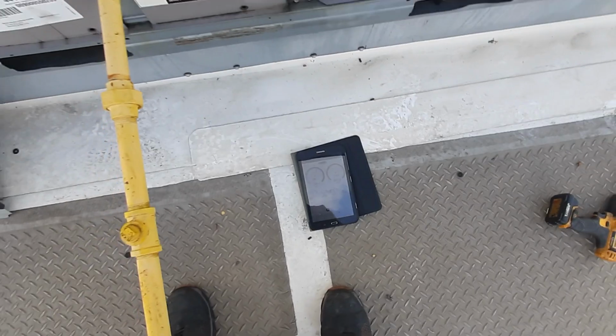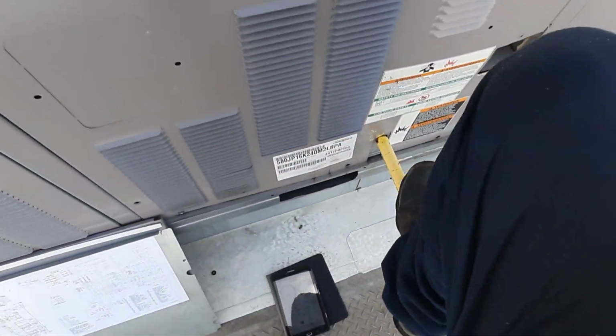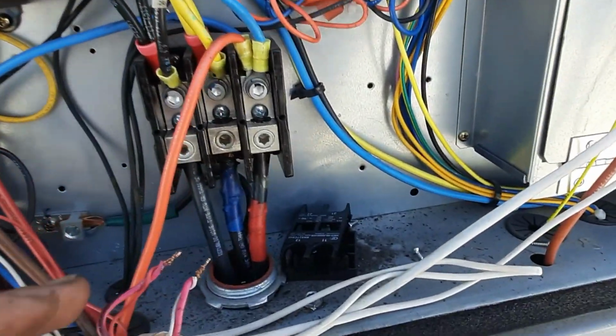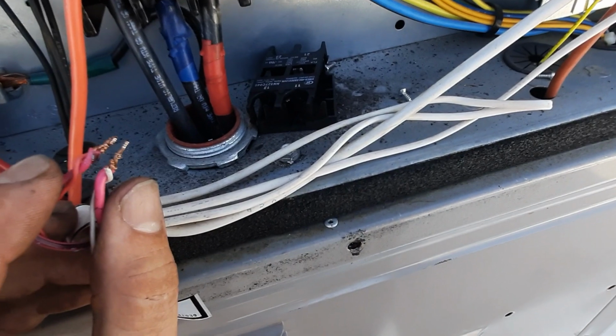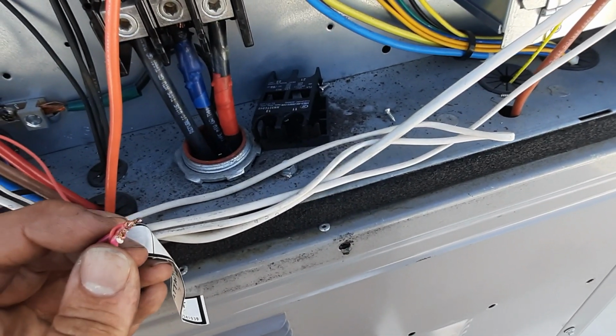I'm going to have to get some more refrigerant. We'll check her again, see where we're at. So I kicked her back on, and we don't have a call for dehum. So basically right now I'm not calling for anything. It's operating just normal. Our humidistat does nothing but close these terminals. So if we go like that, we're in straight dehum mode.